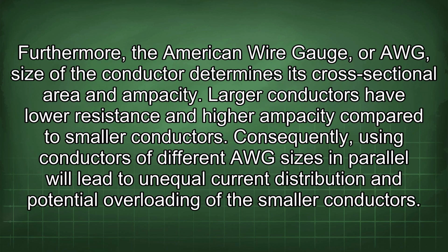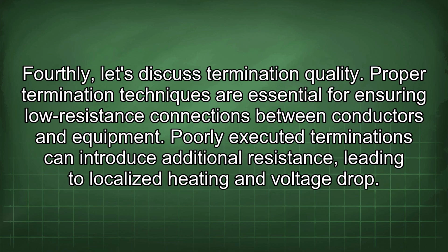Furthermore, the American wire gauge, or AWG, size of the conductor determines its cross-sectional area and ampacity. Larger conductors have lower resistance and higher ampacity compared to smaller conductors. Consequently, using conductors of different AWG sizes in parallel will lead to unequal current distribution and potential overloading of the smaller conductors. Fourthly, let's discuss termination quality.